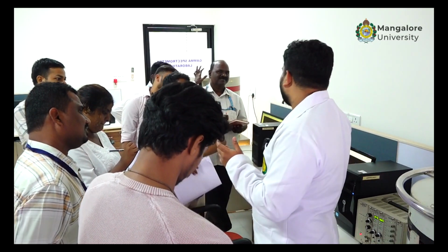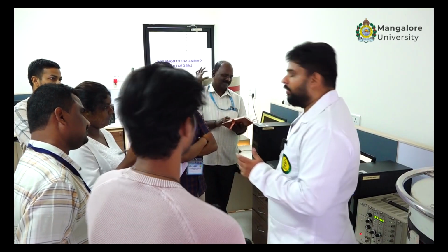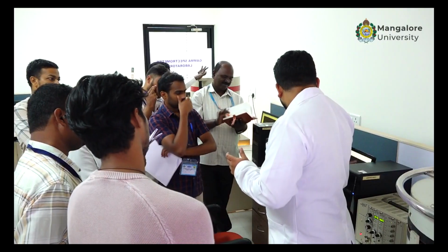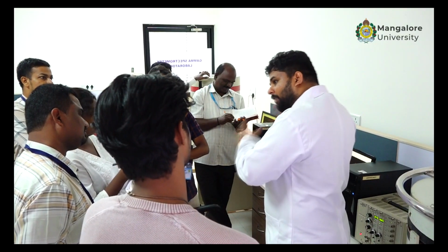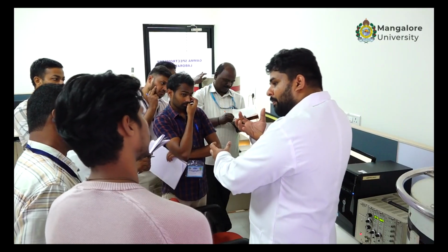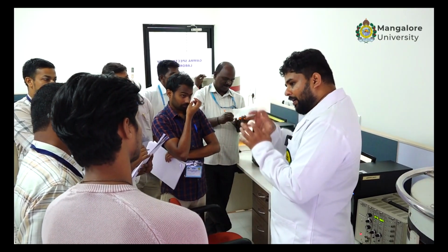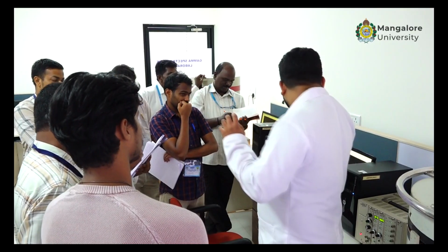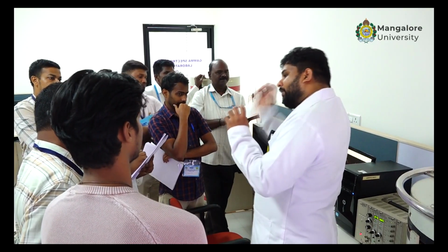However, this peak is thallium 208 and this is the bismuth 214 peak. This peak's energy will contribute some activity to the peak before it. So K40 will be affected by the presence of bismuth 214 or thallium 208, so we have to correct it.